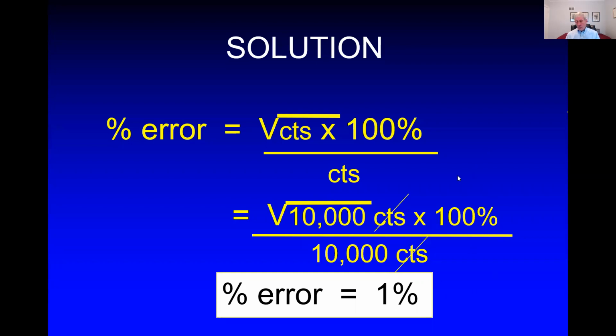Now, here's the reason I chose 10,000. The rule of thumb in a hot lab is that anytime you're counting something in a well counter, let's say chromatography strips, not microcuries or millicuries, but a few 100,000 counts, you want a minimum of 10,000 counts on the coolest piece of your strip, because then you're guaranteed to be counting with a percent error of no more than 1%.